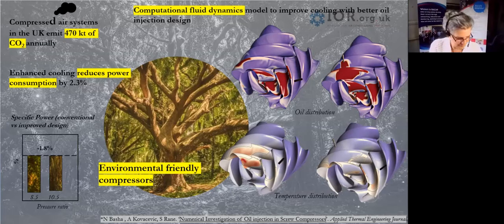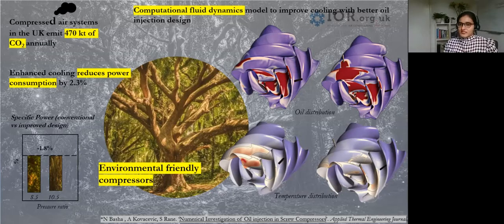My research focuses on twin screw compressors, as these compressors are used in refrigeration and air conditioning systems. Nearly 83% of twin screw compressors are oil injected machines, and oil in these machines is important for cooling, sealing, and lubrication. However, if we have an excess amount of oil, that can add to increased losses and therefore an inefficient machine. So what we need is optimal oil quantity.